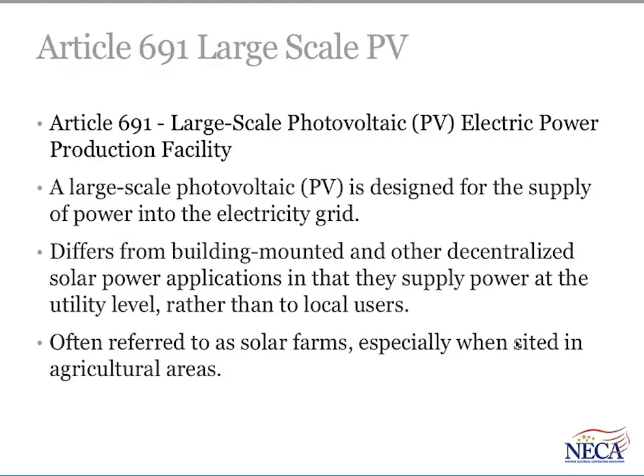Article 691 is new, and this was necessary to provide a set of rules for large-scale photovoltaic electric power production facilities that are being installed in numbers across the country in areas where the sun shines a lot. The deserts of the Southwest are a prime location for these. They're designed for supply of power directly to the electrical grid, and these are in the megawatt size. There's a couple in the Southwest at the 500 and 600 megawatt level, and they tie directly to the grid. They're different from building mounted or other decentralized solar power applications, and they're supplying at the utility level.